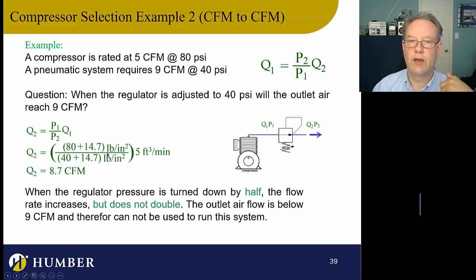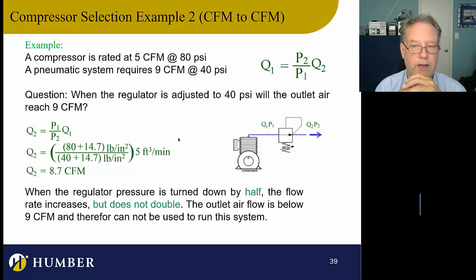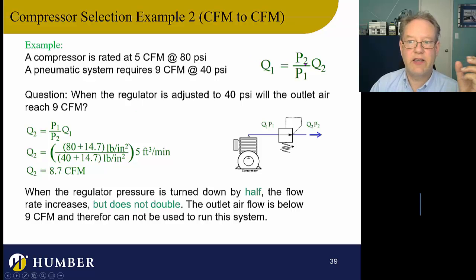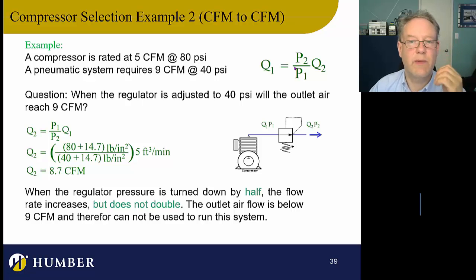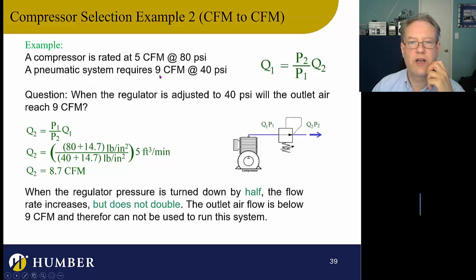First, convert PSI to PSIA: 80 + 14.7 = 94.7, and 40 + 14.7 = 54.7. My pressure is going down, so the flow rate will go up — I need a ratio greater than one, so I put the higher pressure on top and lower on bottom. The result is 94.7 / 54.7 × 5 = 8.7 CFM. We need 9 CFM — this is not going to work.